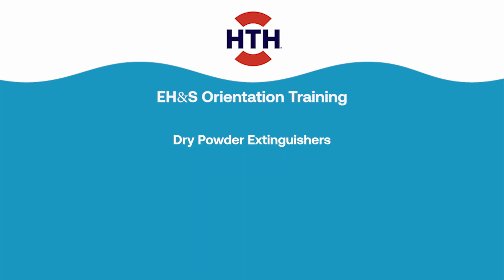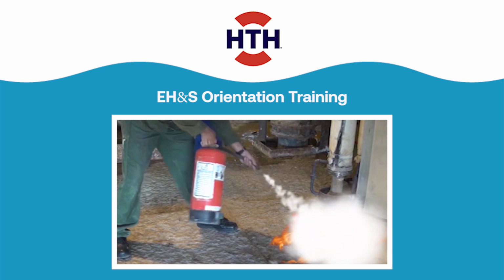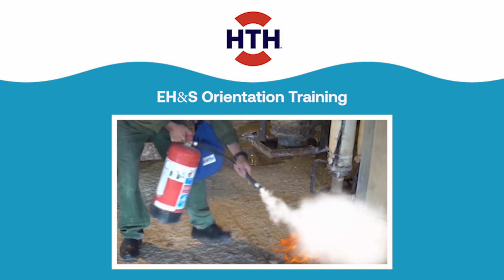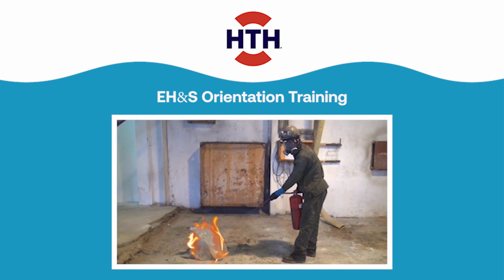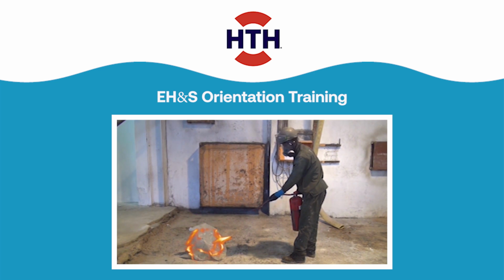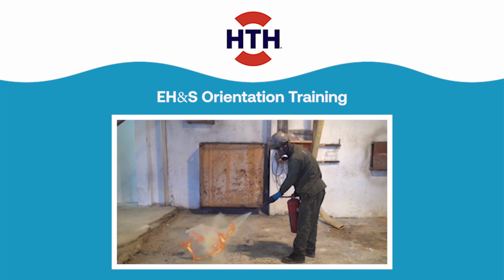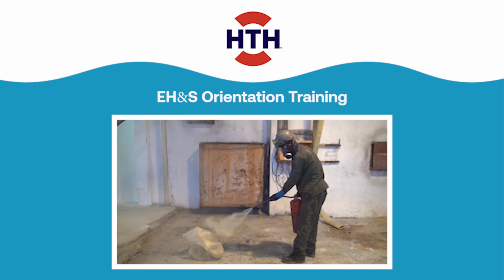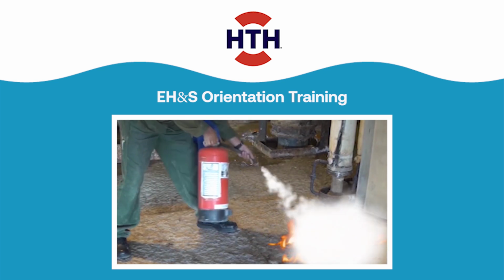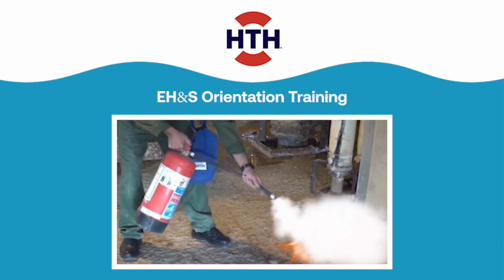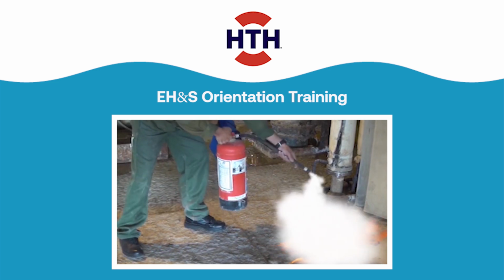Dry powder extinguishers. How to use a dry powder extinguisher. Aim, squeeze, sweep. Pull the pin. Aim the nozzle or hose at the base of the fire from the recommended safe distance. Squeeze the operating lever to discharge the fire extinguishing agent. Starting at the recommended distance, sweep the nozzle or hose from side to side, covering the burning metal until the fire is out.